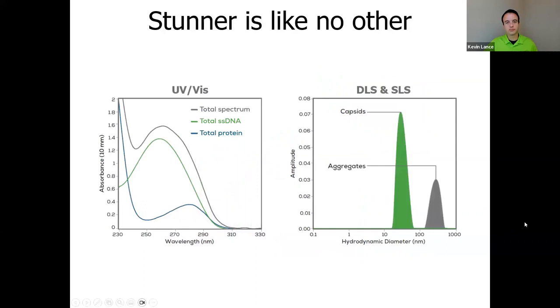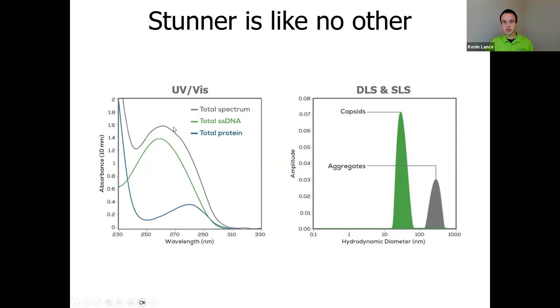When we look at the information more closely, Stunner is unique in the way it analyzes this data. By UV-Vis, we start with the total absorbance spectrum in dark gray, and then Stunner uses advanced spectral unmixing algorithms to break that total spectra down into the underlying DNA and protein components. So instead of just analyzing absorbance at A260 and A280 and hoping for the best, Stunner knows your sample is AAV and can break it down into exactly what the absorbance signal is for your DNA and for your protein. On the DLS side, we get a size distribution showing our capsids as the predominant peak, and in this example, some aggregates present as well.